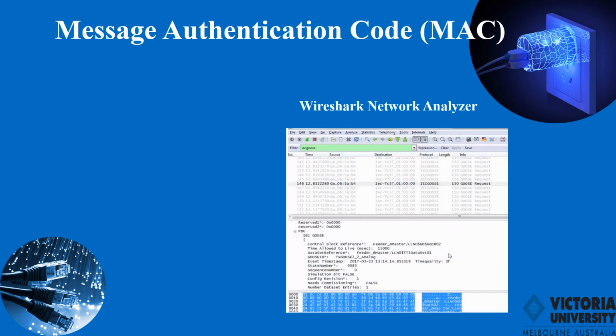The Wireshark software will be used to analyze the packets from the communication protocols GOOSE, MMS, and SV. The packets of the GOOSE message will be monitored from the physical ports of the Ethernet and wireless network. The Wireshark network analyzer shows all the specific details of a GOOSE message, like GOOSE control blocks, time allowed to live, dataset, GoID, timestamp, status number, sequence number, and the different data entries of a GOOSE message.